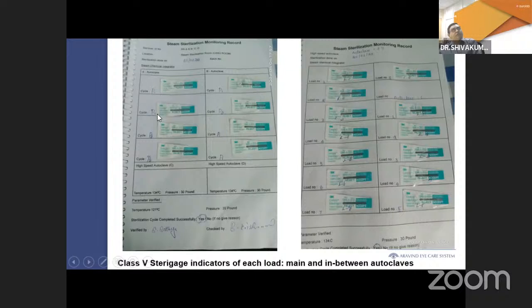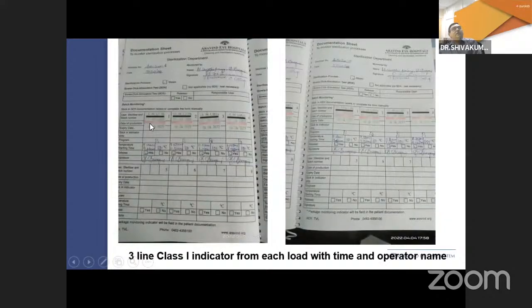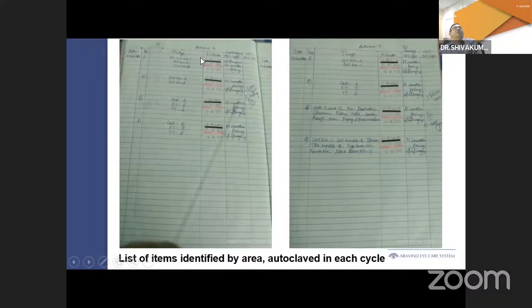This is the Sterigage from each of the cycles from each of the autoclaves, and this is from each of the cycles from the in-between sterilization in the high-speed autoclave. Similar 3-line tapes from each of these cycles, but this also contains the timing of the cycle, as well as the person who has carried out the loading and the unloading. And this is another register, again with a 3-line tape, and this shows all the bins from which OT have been loaded in that particular cycle, and this is for each of the autoclaves. So these records help in tracking back as to which load or which cycle could have been defective.